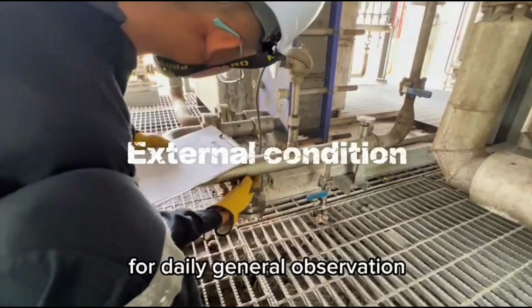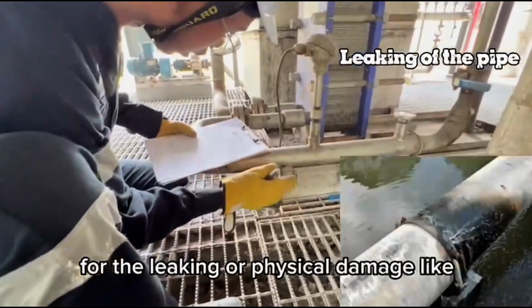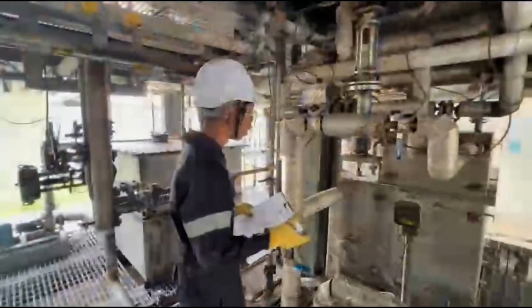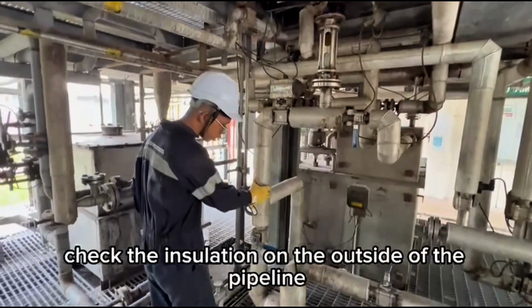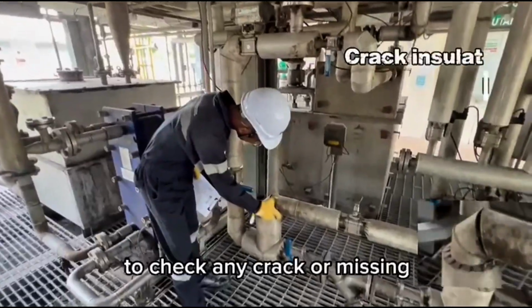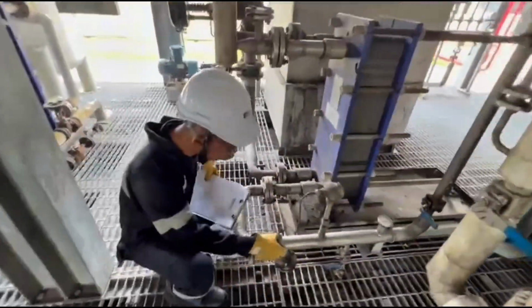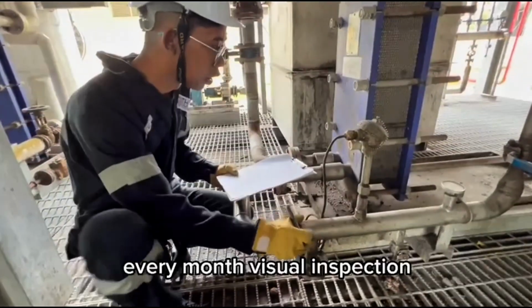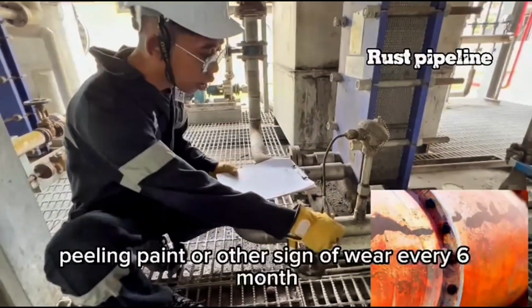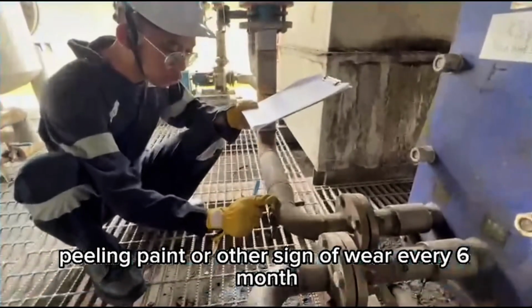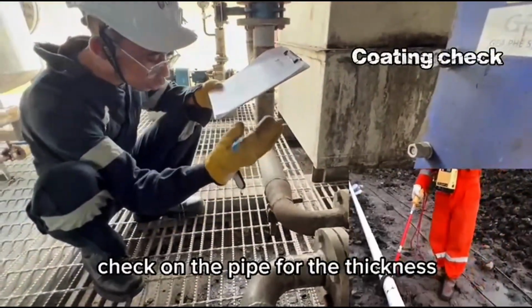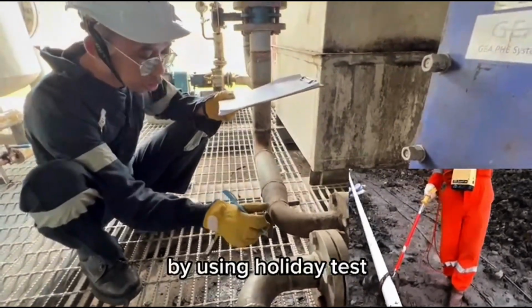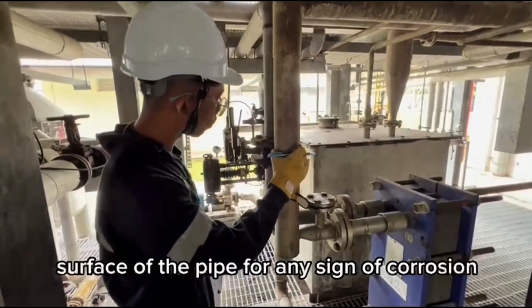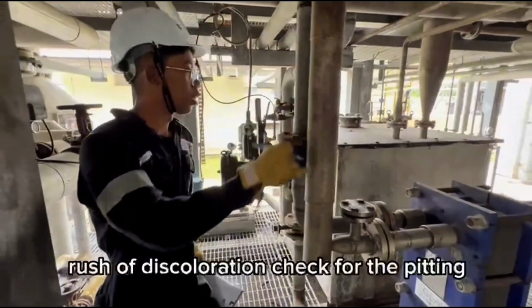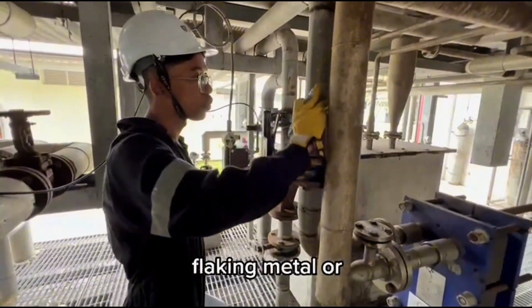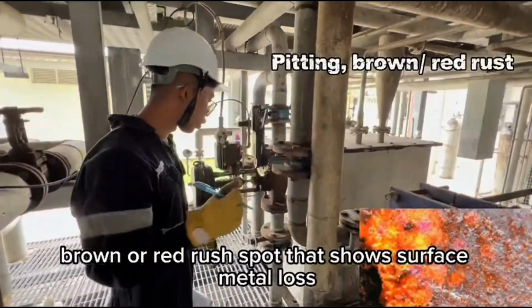For daily general observation, they look at the outside of the pipe for leaking or physical damage like dents or cracks. Every week, the maintenance team checks the insulation on the outside of the pipeline for any cracks or missing parts. Every month, do a visual inspection of the pipe surface, checking for rust, peeling paint or other signs of wear. Every 6 months, inspect the coating on the pipe for thickness by using a holiday test. Yearly, look at the outer surface of the pipe for any sign of corrosion, rust or discoloration. Check for pitting, flaky metal or brown or red rust spots that show surface metal.